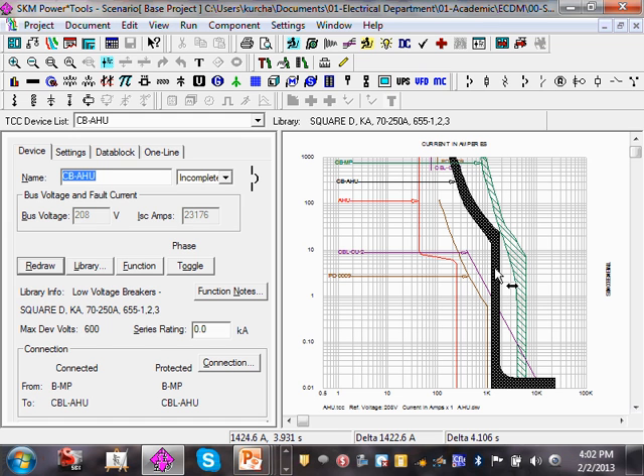Now look at the blue curve. I want you guys to cross-reference the blue curve right here. Now what's right here, very clearly the black curve is going to protect it, right? Because if you have a short circuit anywhere in this area, the circuit breaker will trip before you reach the damage curve. Clear? Now what's going to protect it right in here? Hold your horses. This is an air handling unit. What do we have for an air handling unit?